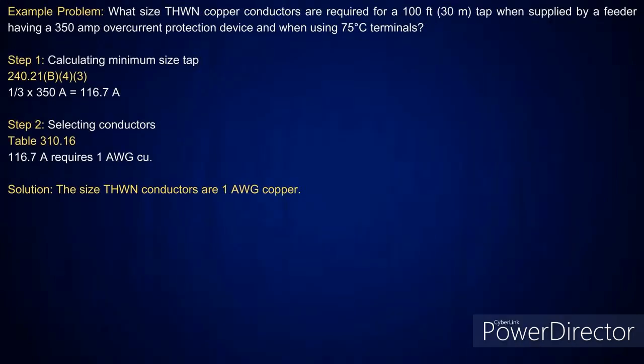Now look at this. This is a 100-foot tap. I said, even if you go up to 100 foot, what do I take it at? A third. So I've got a 350 amp overcurrent device upstream. Take it at a third. That gives me 116.7 amps.